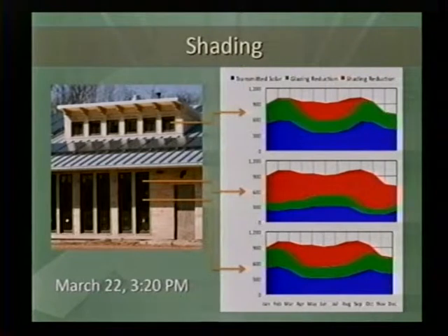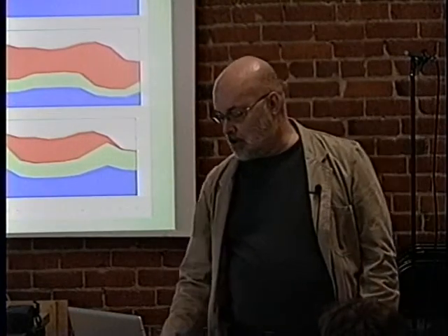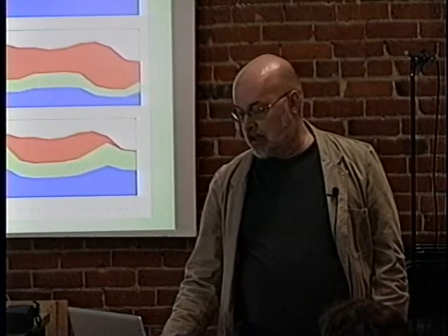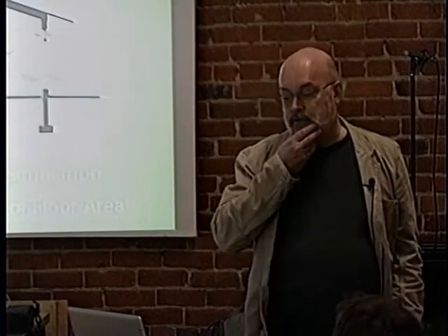We did work quite a bit on shading strategies. I think it's critical to reduce the cooling demand in the summer by proper control and shading. Most mechanical engineers treat the perimeter of a building as a higher cooling load than the interior of the building because of solar gains. And it's actually hard to find mechanical engineers that you can work with on shading strategies and reduction of those gains because they figure, oh, they'll go out in value engineering and I've got to be sure I have enough equipment, on the assumption that there's no solar control on the glass. But we work very hard to try to get a good reduction of the solar gain in the summer. It does take it out somewhat in the winter, but I think that's a critical part of good design.